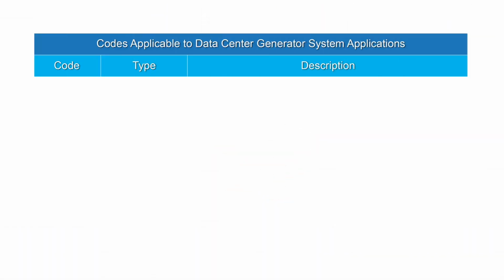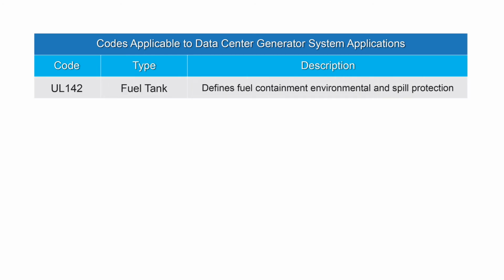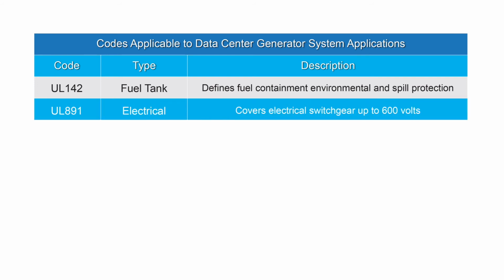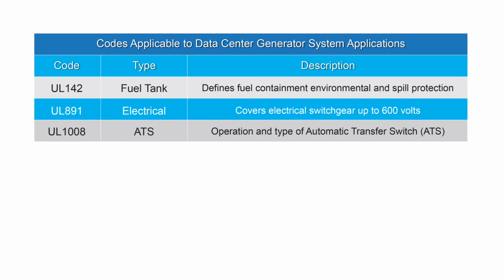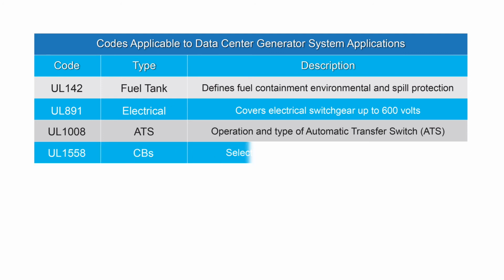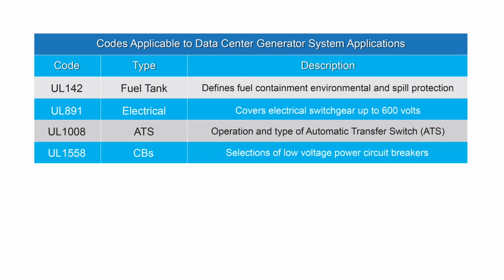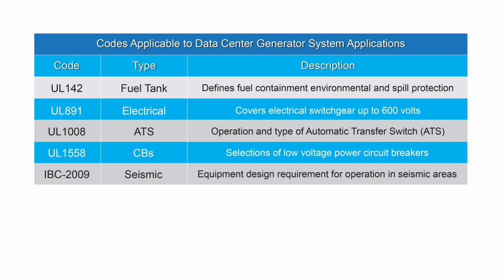Important codes applicable to generator systems powering data centers include UL 142 for above-ground steel tanks with spillage containment, UL 891 for safety criteria for electrical switchgear up to 600 volts, UL 1008 for automatic transfer switches, UL 1558 for low-voltage power circuit breakers. Critical installations in seismic areas will also be subject to International Building Code IBC 2009.